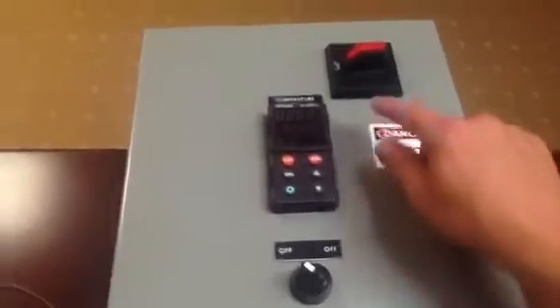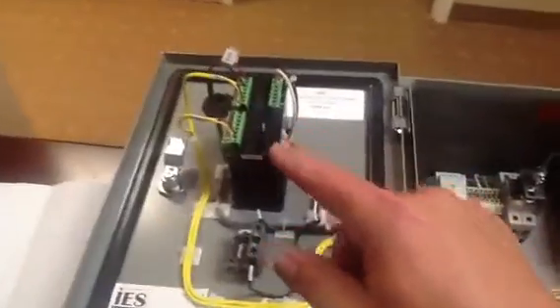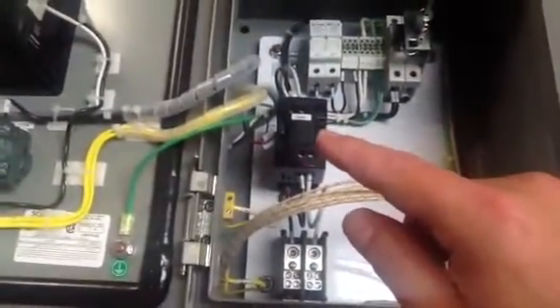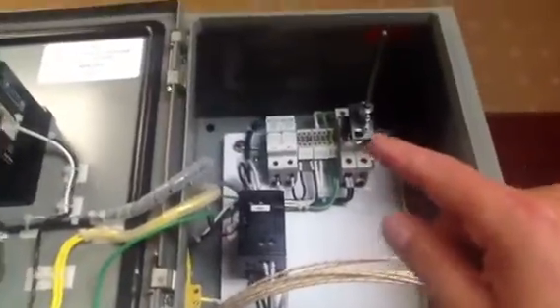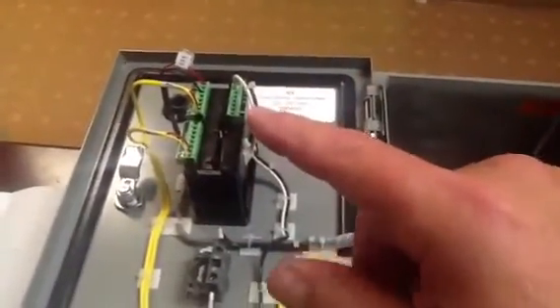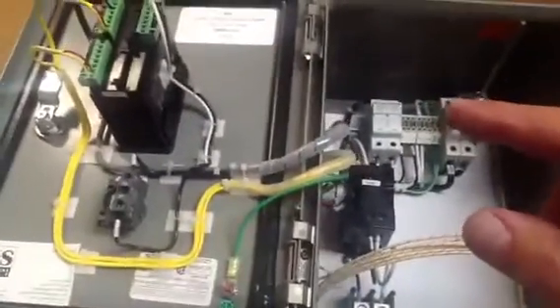So inside of this, we have these two inputs here, and this is just set up for 110 volts in, and this has a cascade control, Watlow temperature control, on-off switch, and a power disconnect. So if we look inside the actual panel itself, we have the temperature control, we have a solid-state switch, solid-state relay, some fuses, and the main power disconnect. So the main power is turned on, power flows through a control switch, goes up to this switch that turns power on to the controller itself, and it allows energy to flow through the system.